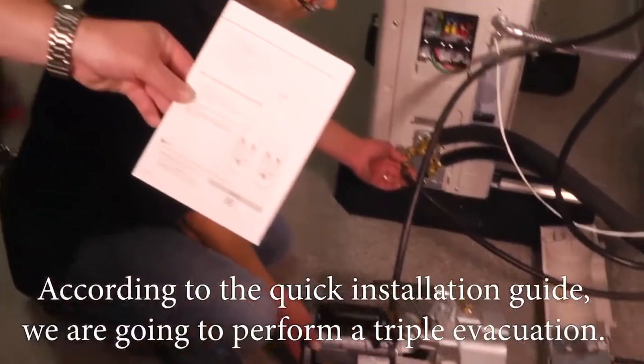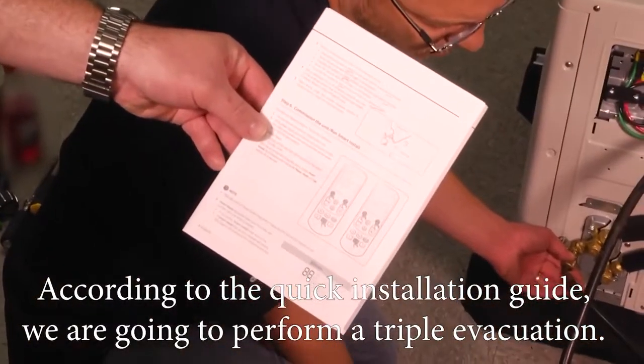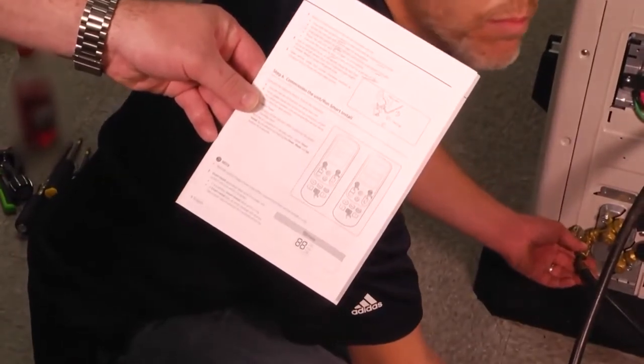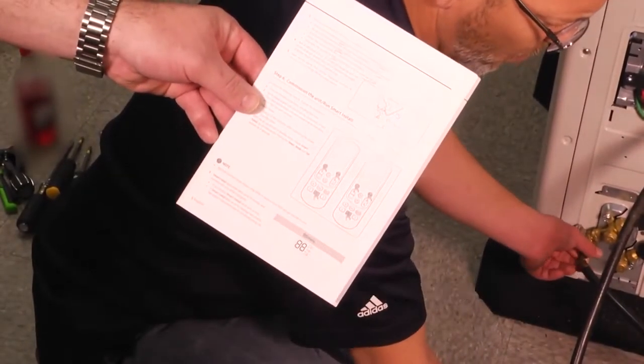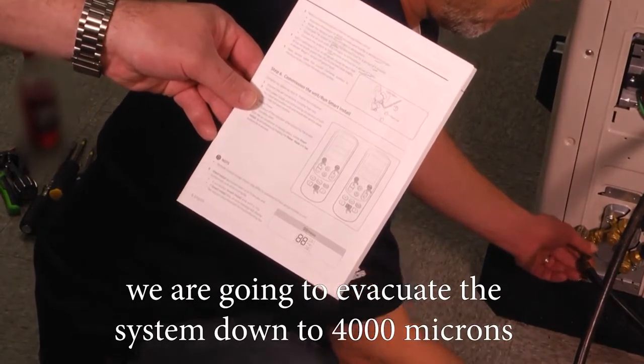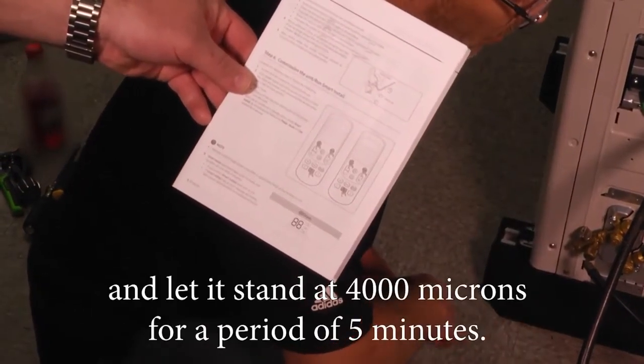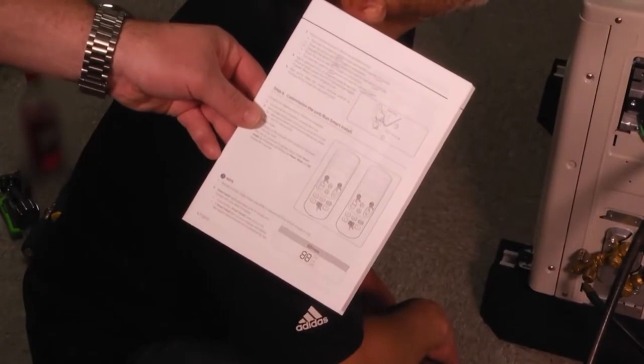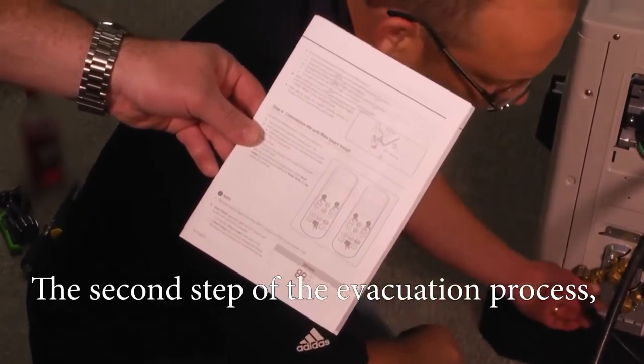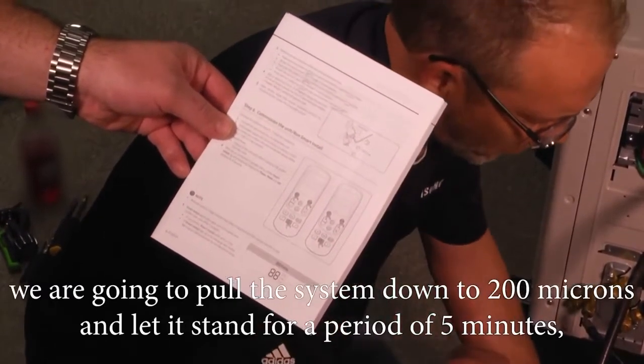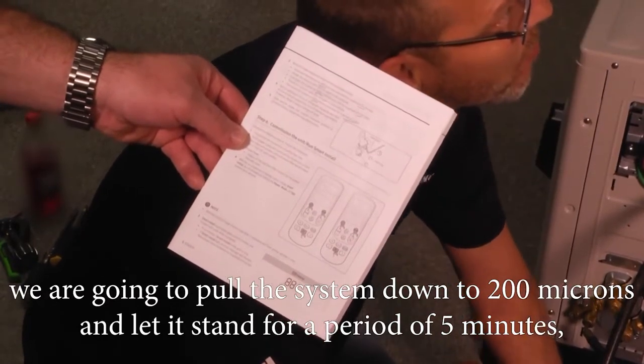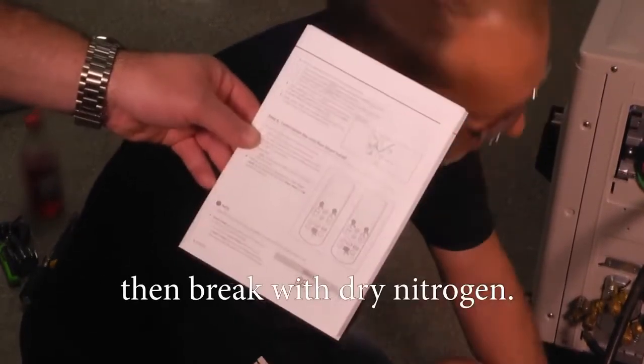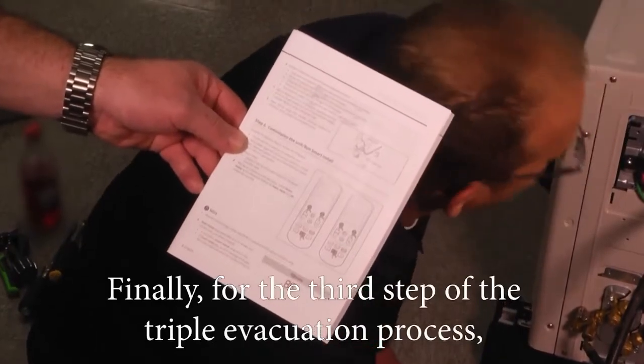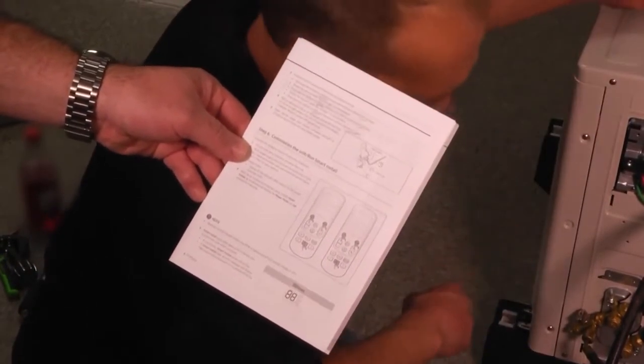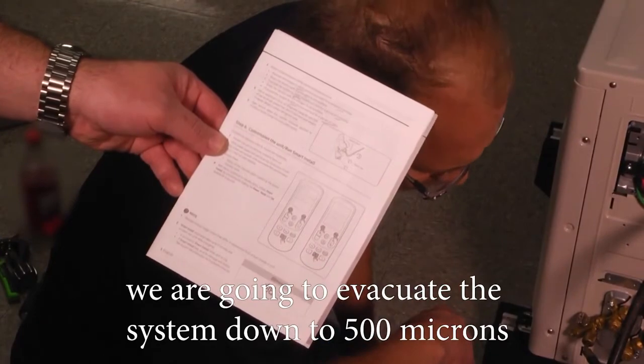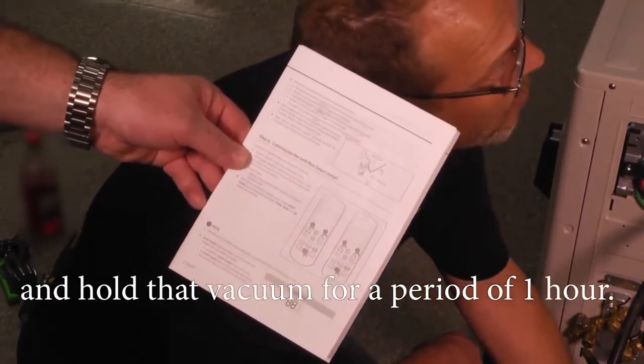According to the quick installation guide, we're going to perform a triple evacuation. The first part of the evacuation, we're going to evacuate the system down to 4,000 microns and let it stand at 4,000 microns for a period of 5 minutes. The second step of the evacuation process, we're going to pull the system down to 200 microns and let it stand for a period of 5 minutes, then break with dry nitrogen. And then finally, for the third step of the triple evacuation process, we're going to evacuate the system down to 500 microns and hold that vacuum for a period of 1 hour.